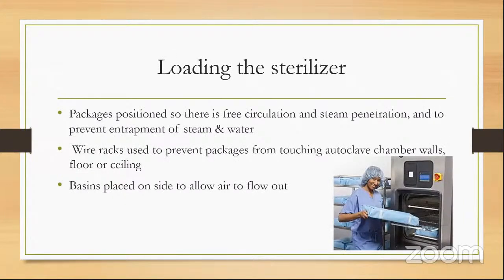In terms of loading the sterilizer, packages should be positioned so there's free circulation and the steam can penetrate, and there is no entrapment of steam and water. Wire racks are used to prevent packages from touching the autoclave chamber walls, the floor of the autoclave, or the ceiling, and basins are typically placed on the side to allow air to flow out of it.